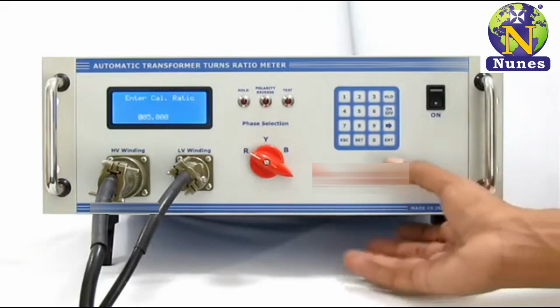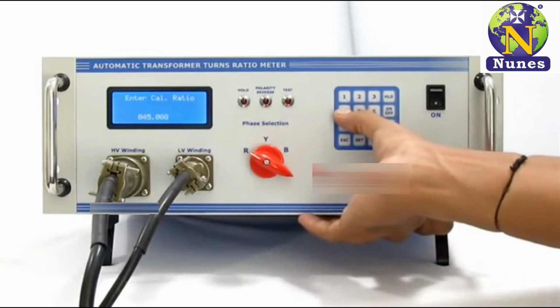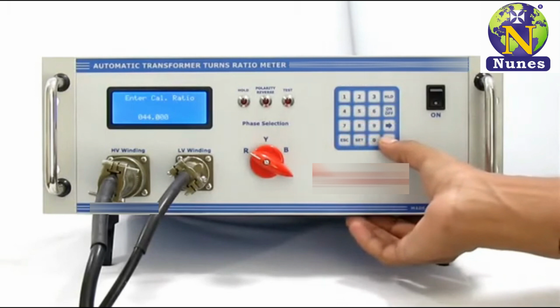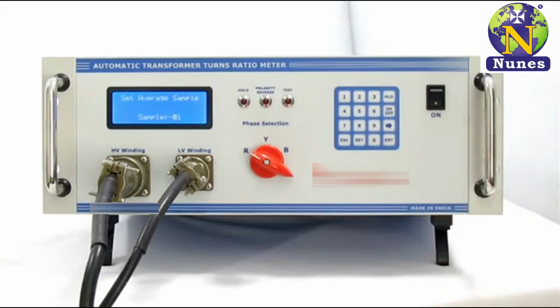Step 6. Please enter transformer ratio using this numeric keypad as per your transformer's calculated ratio. Then press the ENT enter button to save this calculative ratio in the memory of VTRM. Step 7. Now you can see set average sample mode in the display. Step 8. Set average sample from 1 to 10 as per your requirement using this numeric keypad. This function is useful when your auxiliary power supply voltage has too much fluctuation. Select 10 samples for highest fluctuation and select 1 for lowest fluctuation.